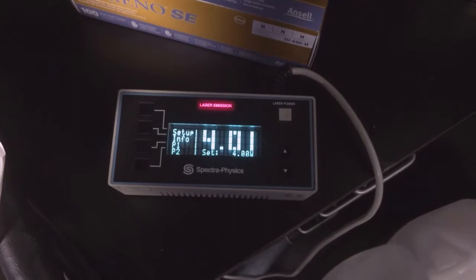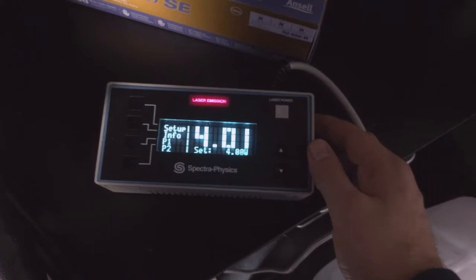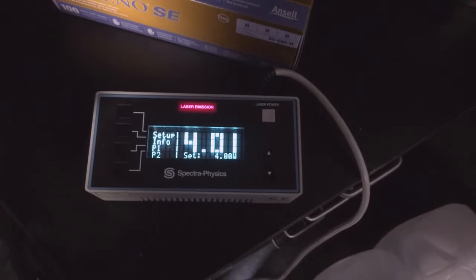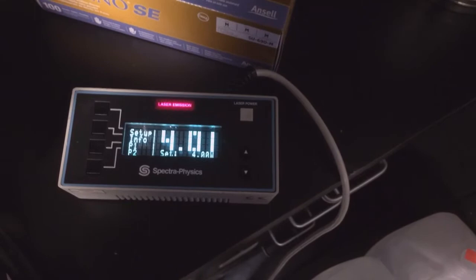When the laser is aligned well to see it lase, the threshold is about 2.5 watts. I suggest setting the green power to 4 watts for daily alignment so that there is sufficient red light coming out when it is aligned. And then you can compare the day-to-day power values with those before knowing that you are always putting in the same pump.